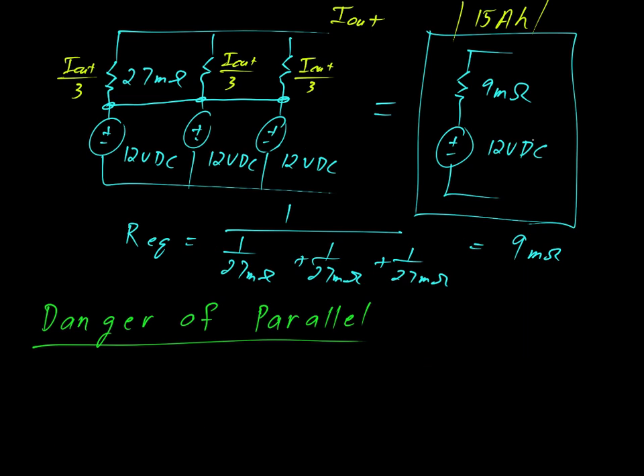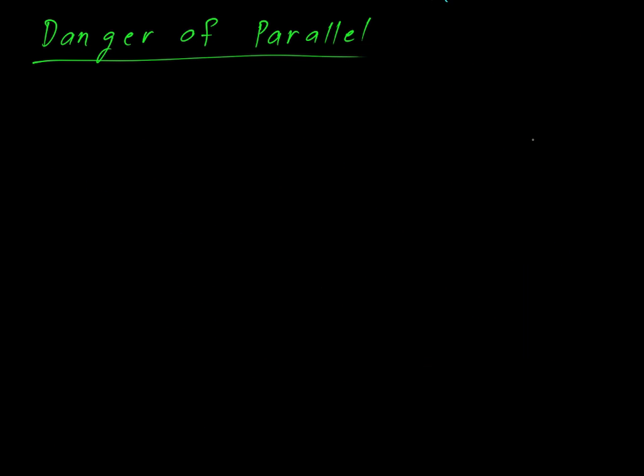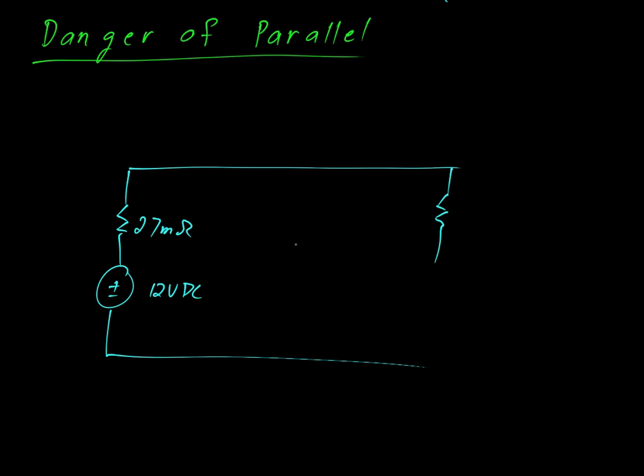Moving on, let's talk about the dangers of paralleling batteries. And for this discussion, let's assume that you've done something silly like connect a 6 volt battery in parallel with a 12 volt battery. So we'll keep our PB5-12 battery, which you'll recall had a 27 milliohm resistance and a nominal 12 volt DC voltage source. And we're going to connect this up with a PB5-6, which is a slightly smaller 6 volt battery.